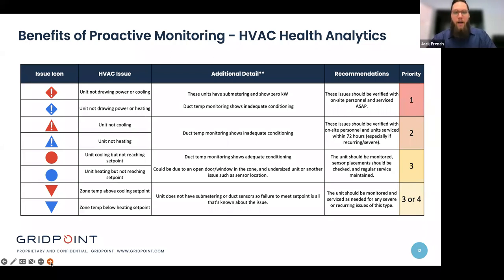insulation coming in. And then the same could be true with heating season. If you have a thermostat located on an exterior wall that's not well insulated, you may see that the zone temperature is pretty far below the heating set point. Even though the unit is supplying warm air to the space, the zone is still below heat set point. It could mean that you have a sensor that's influenced by some adjacent cold air infiltration. Or, of course, if thermostats or sensors are located too close to doors that are heavily trafficked, that can influence the sensor as well.